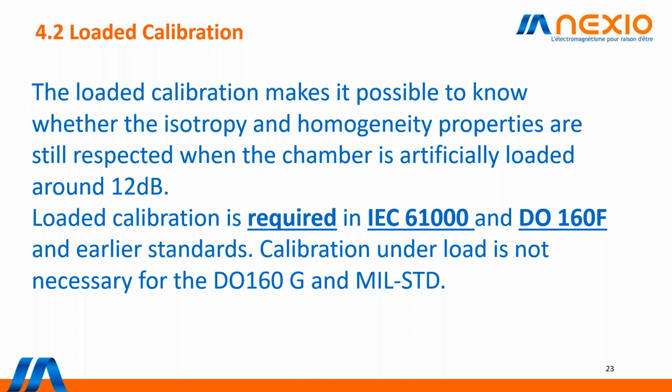A loaded calibration is required for the IEC 61000 and DO160F and earlier standards. Calibration under load is not necessary for the DO160G and MIL-STD.